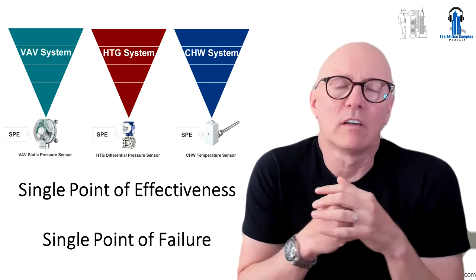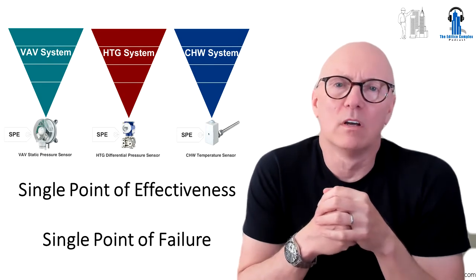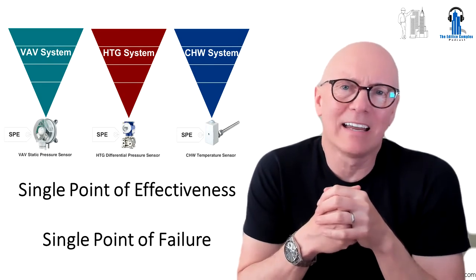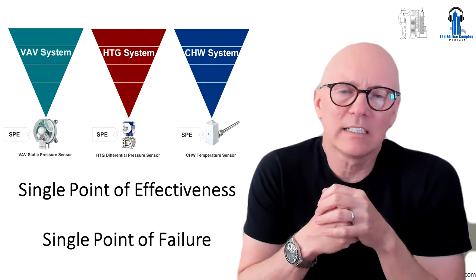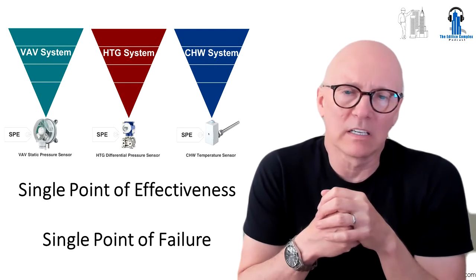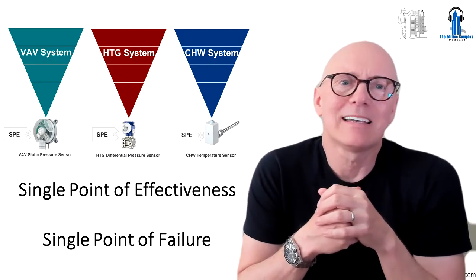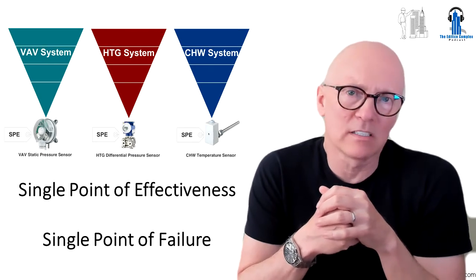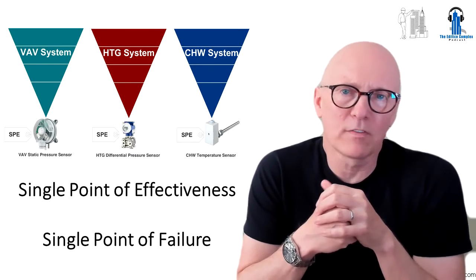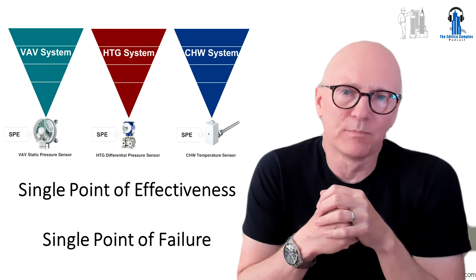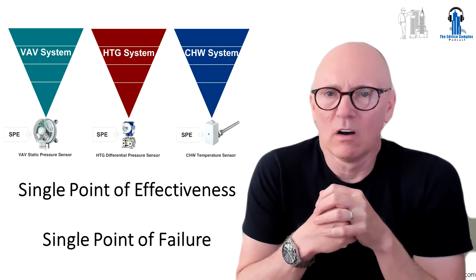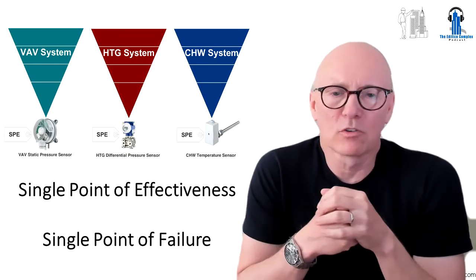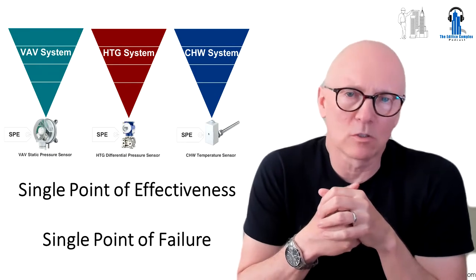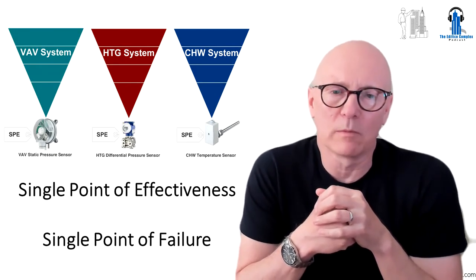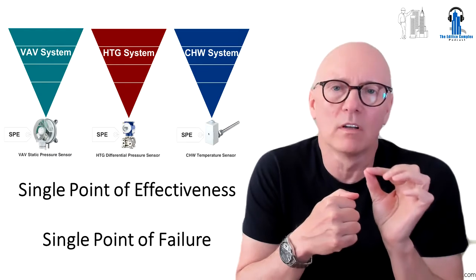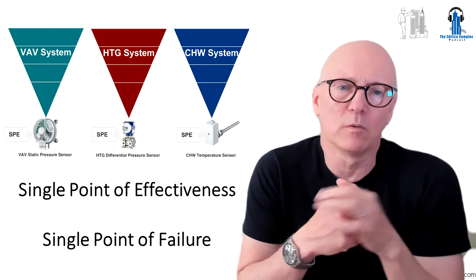So if you take a VAV system, that whole system and its performance and its energy consumption is really determined by several things, but one of the biggest factors is the correct location of the static pressure sensor and its derived optimum set point during commissioning. If you set it too high, the system will be overpressurized, it will use too much pressure. If you set it too low, the boxes won't be floating and operating properly. So there is a sweet spot that can only be determined via field testing.